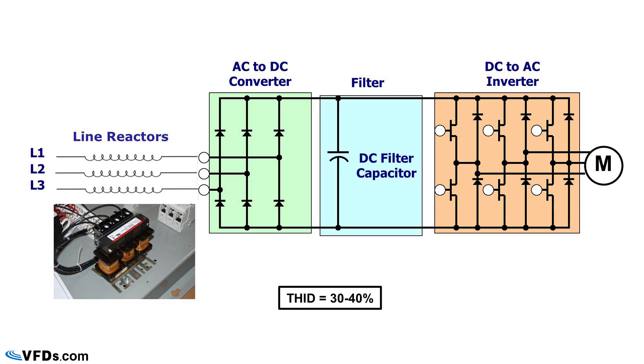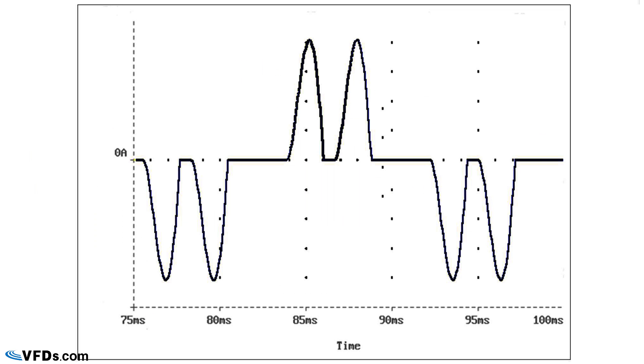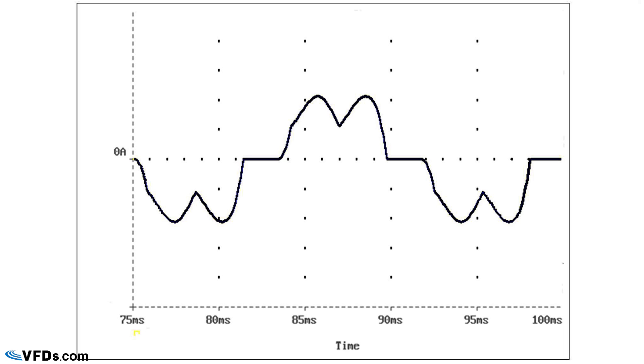So this reduces our harmonics from 100% down to maybe 30-plus percent. Let's take a look at the actual waveforms that we get. This is a waveform without reactors, and you can see for a three-phase input drive, we get two large pulses of current on the positive side and then two on the negative side with each cycle. If we add line reactors to this, you'll notice that it makes a considerable improvement. Now this is not a sine wave — it still has some power system pollution, but not nearly as bad as the previous slide. This eliminates two-thirds of our harmonics.